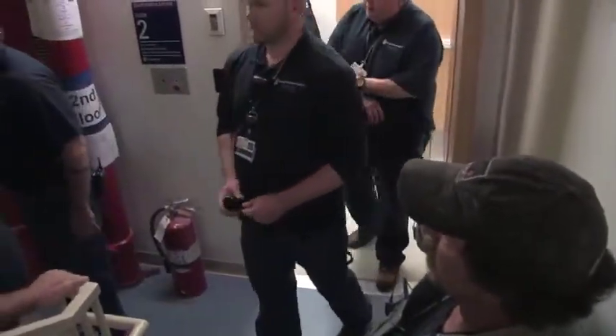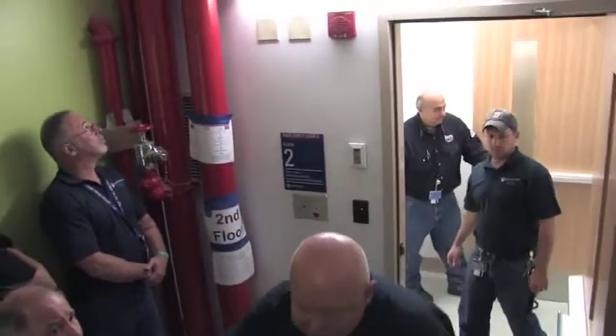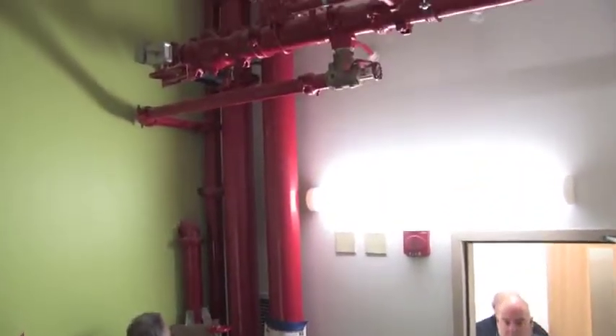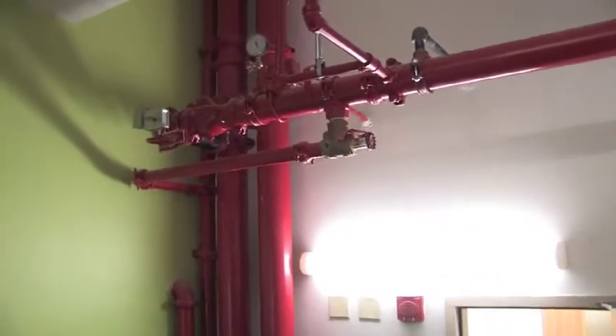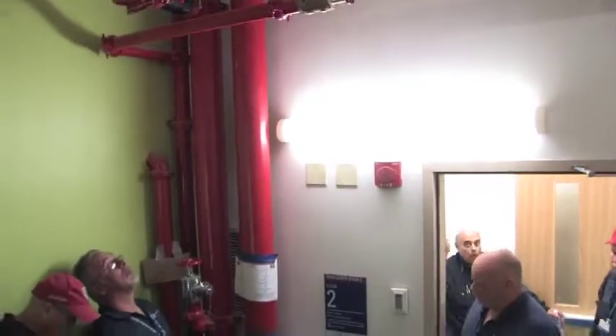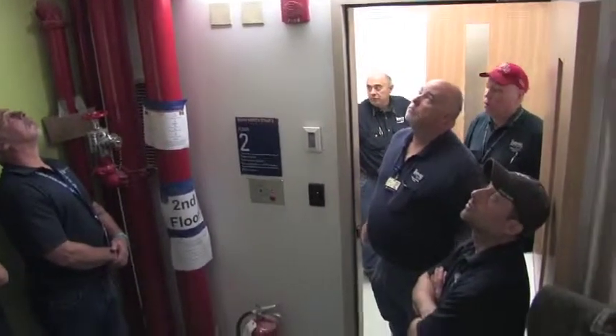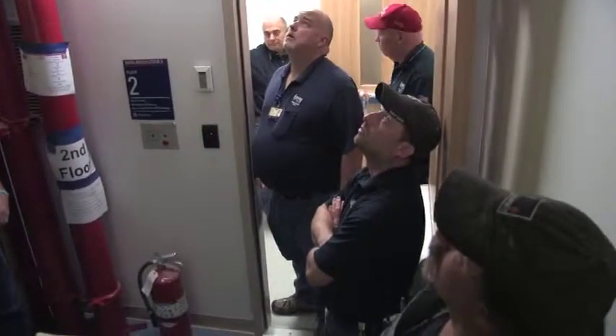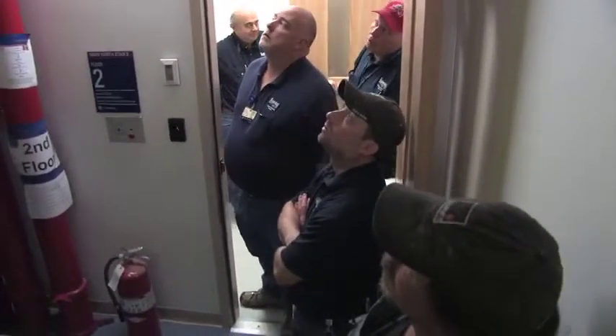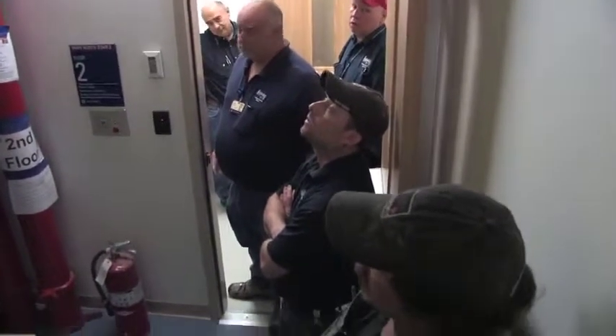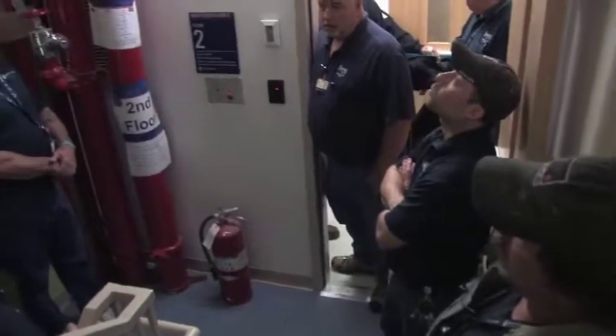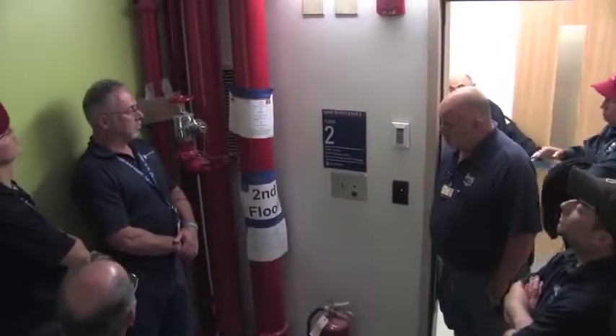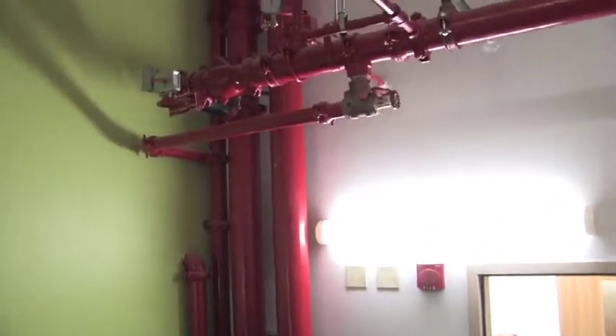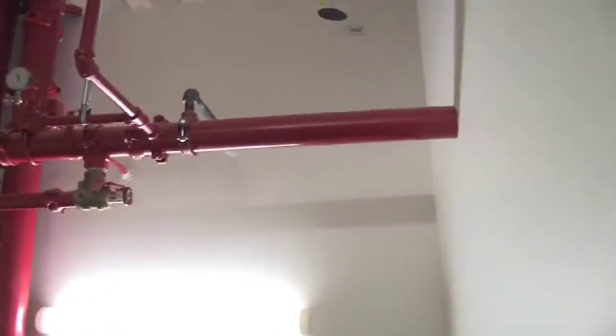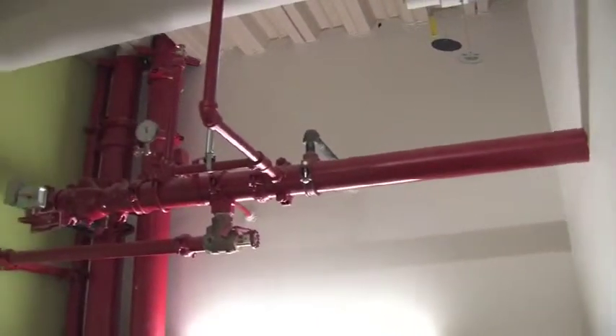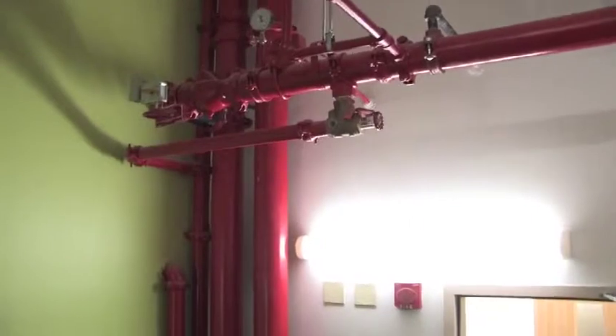Yeah, once again, all the floors are dual fed. So when we first came up the stairs over there, I showed you that's one of the 2 valves you got to shut off. And those tags tell you that too. When you look on them, it says you got to shut off 2 valves to work on the system. And they're combination standpipes, so you got your fire department valves on them and your sprinklers coming off of them. The pipe to the right is obviously the express heading up to the high system. So that's the high system, because this one's got the sprinklers coming off of it.